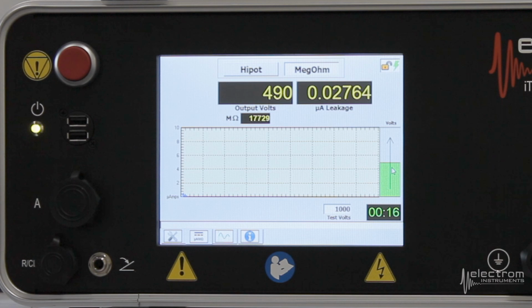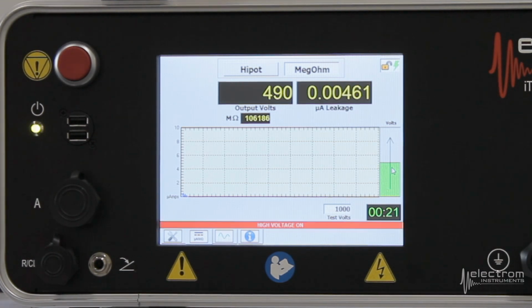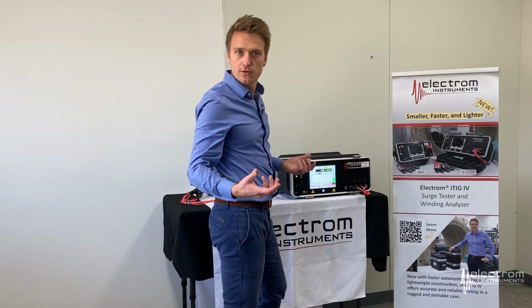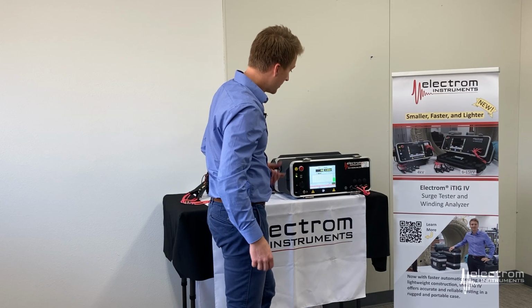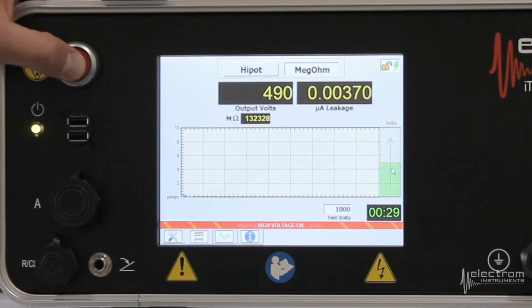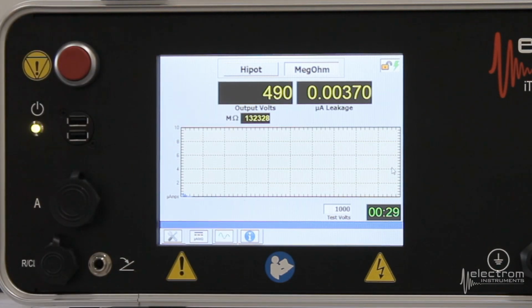Something like that. Now we can sit here for as long as we feel like. Leakage current is low, it's relatively stable. There's no reason to expect this will change anytime soon. So I'm happy with that. Press the red button, automatically discharges the windings and reports the megohms. In this case, extremely high megohms because the leakage current was so low. So this motor, the insulation system is clean and dry. We're safe to proceed to high voltage testing.